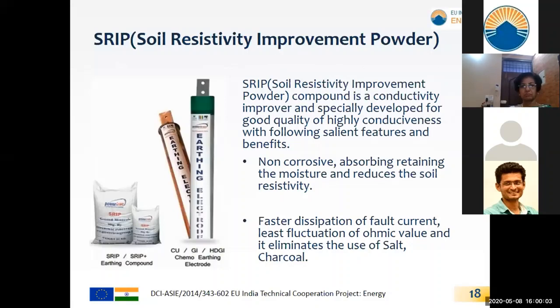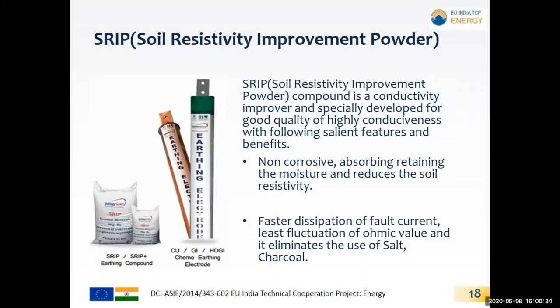Soil resistivity improvement powder. In conventional earthing, we use salt and charcoal to reduce the soil resistivity and the ohmic value. Here in maintenance free earthing, we use a soil resistivity improvement powder, which is non-corrosive and absorbs and retains moisture. So in conventional earthing, we use a plate of copper or GI, and then we fill with soil and charcoal. Here we are using the soil resistivity improvement powder.